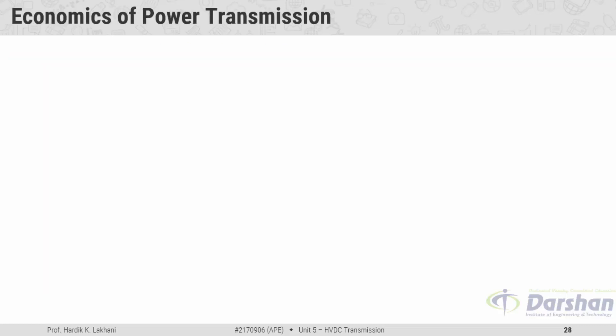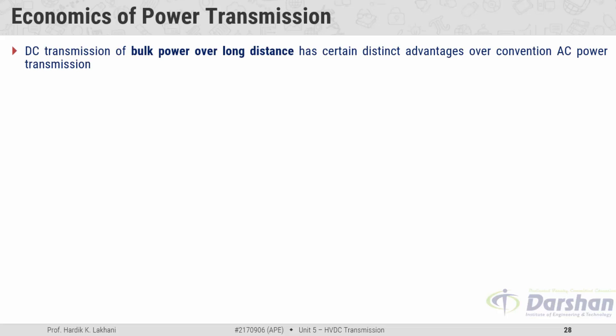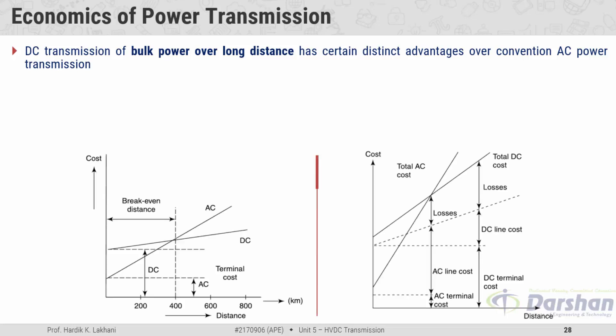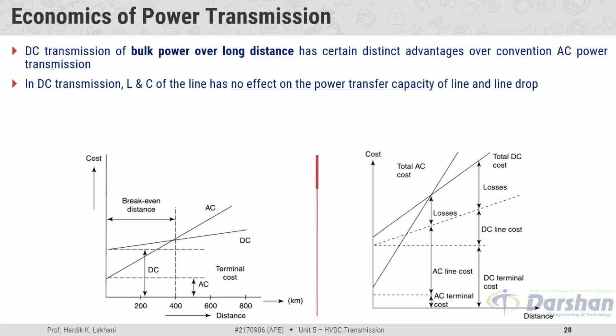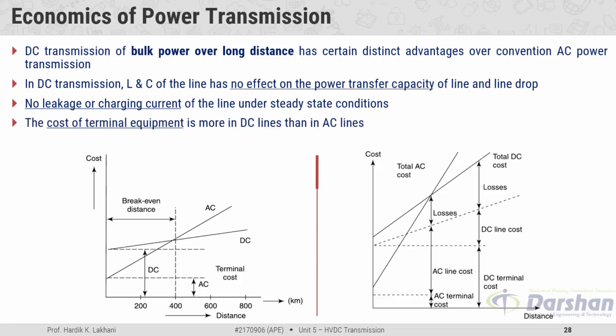The first factor is economics of power transmission. The DC transmission of bulk power over long distances has certain advantages over conventional AC power transmission. In DC transmission, the inductor and capacitor of the line has no effect on power transfer capacity and line drop. There is no leakage or charging current of the line under steady state conditions. The cost of terminal equipment is more in DC lines than in AC lines, so a cost comparison between AC and DC transmission systems is made using graphs.